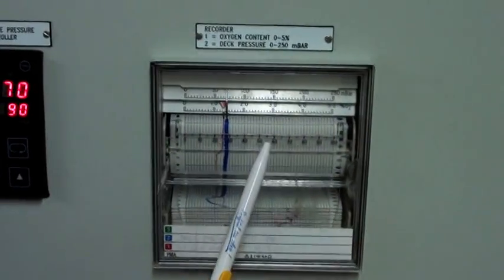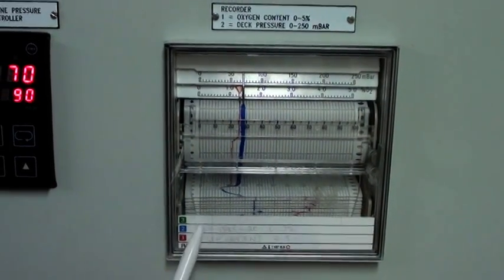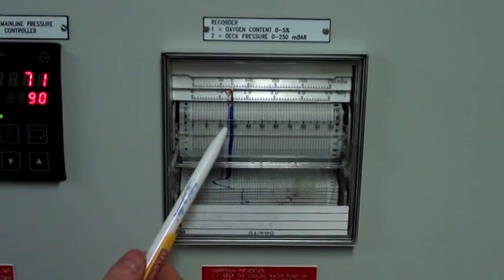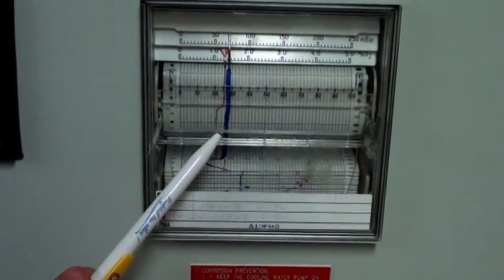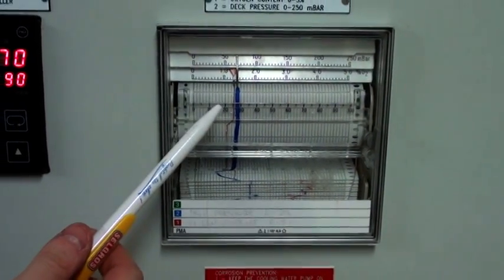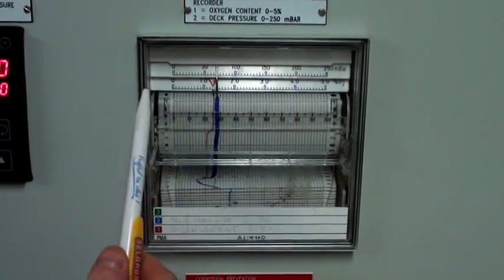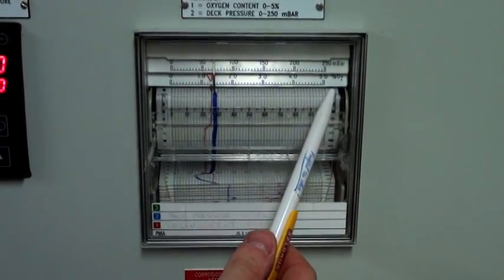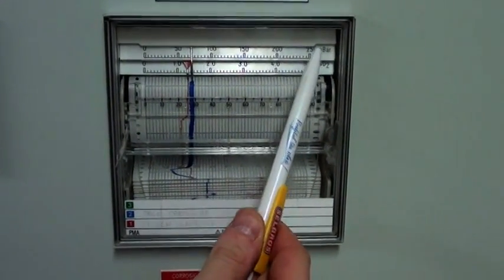On the starboard side you have the recorder of inert gas with two indicators. The blue one is indicating the pressure in the line, and the red one is indicating the oxygen content. So the oxygen content scale is from 0 to 5%, and the pressure indicating scale is from 0 to 250 millibars.